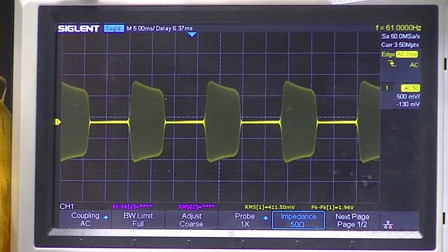All of them used line sync because it's available. We didn't have much battery powered equipment back then. And most sweep generators of that era were synchronized to the power line.